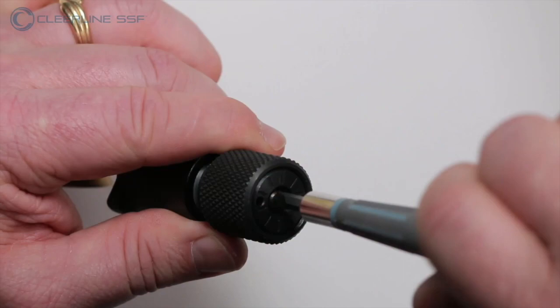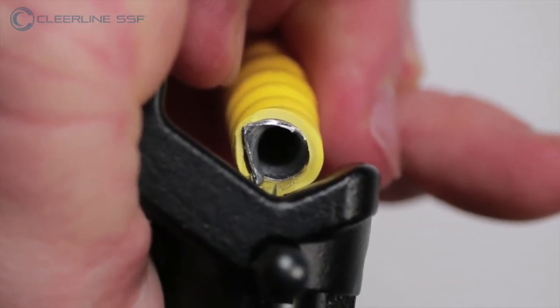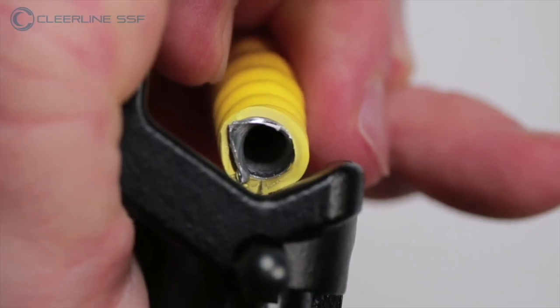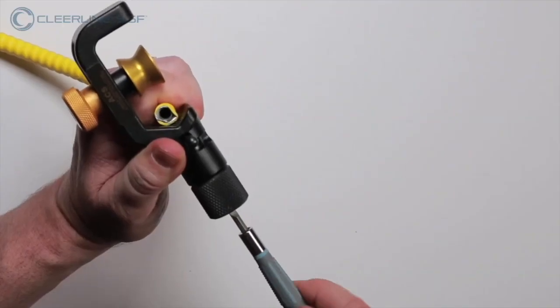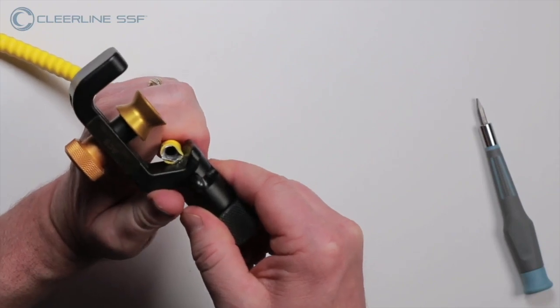Loosen the allen screw and adjust the blade height by turning the flathead screw located on the base of the slitting tool so it approximates no more than the thickness of the cable jacketing. Avoid setting the blade too high and then tighten the allen screw to secure the blade.